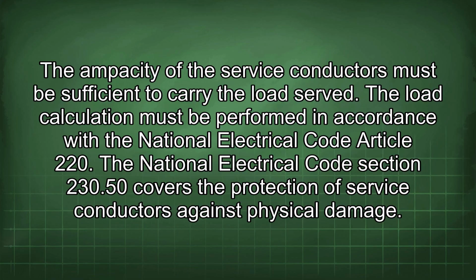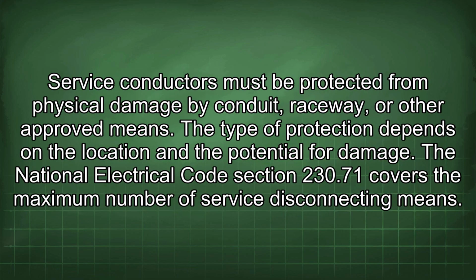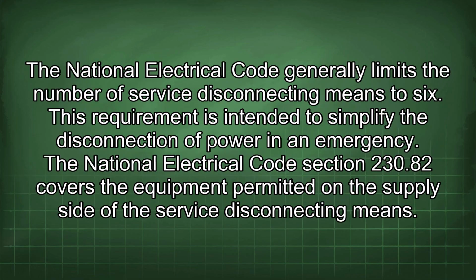The National Electrical Code Section 230.50 covers the protection of service conductors against physical damage. Service conductors must be protected from physical damage by conduit, raceway, or other approved means. The type of protection depends on the location and the potential for damage. The National Electrical Code Section 230.71 covers the maximum number of service disconnecting means. The National Electrical Code generally limits the number of service disconnecting means to 6. This requirement is intended to simplify the disconnection of power in an emergency.